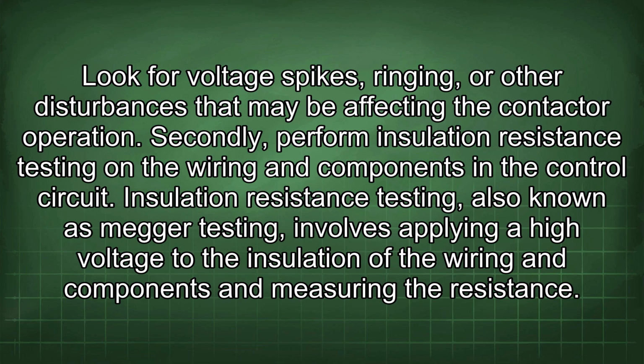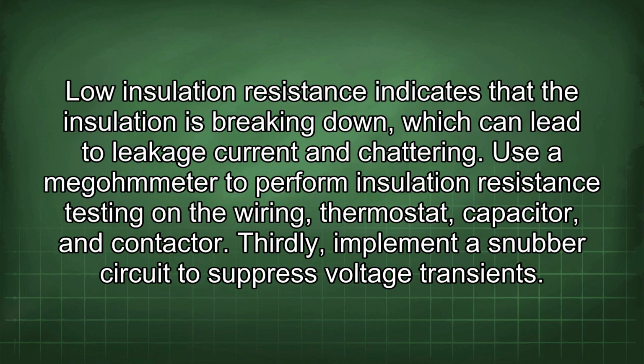Secondly, perform insulation resistance testing on the wiring and components in the control circuit. Insulation resistance testing, also known as megger testing, involves applying a high voltage to the insulation of the wiring and components and measuring the resistance. Low insulation resistance indicates that the insulation is breaking down, which can lead to leakage current and chattering. Use a megohmmeter to perform insulation resistance testing on the wiring, thermostat, capacitor, and contactor.